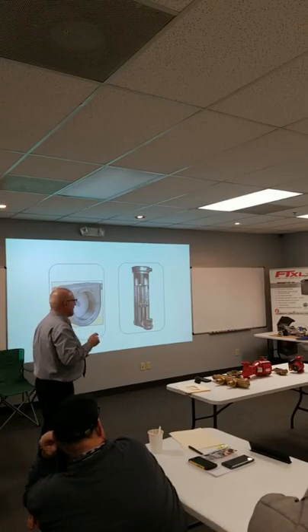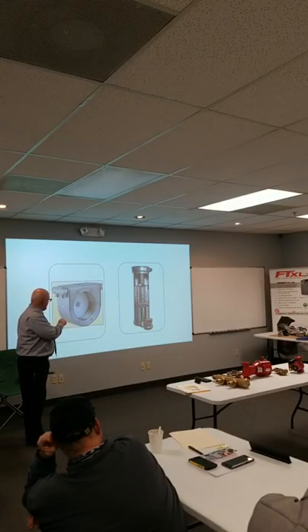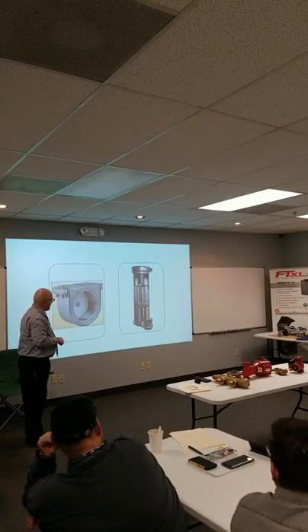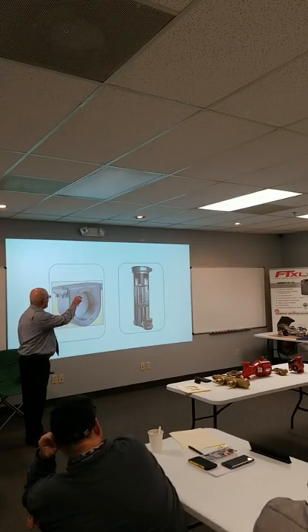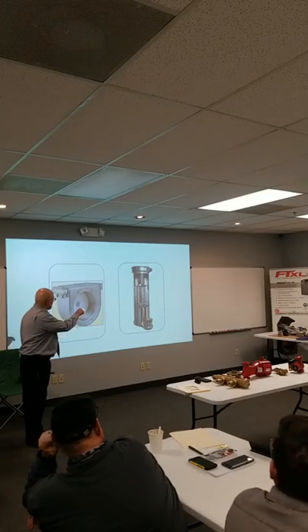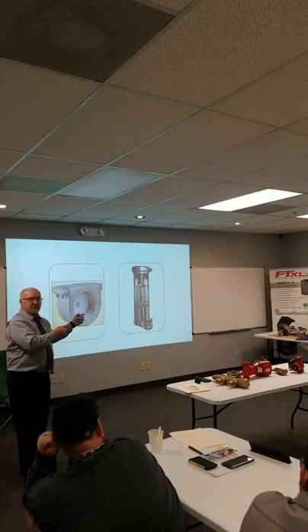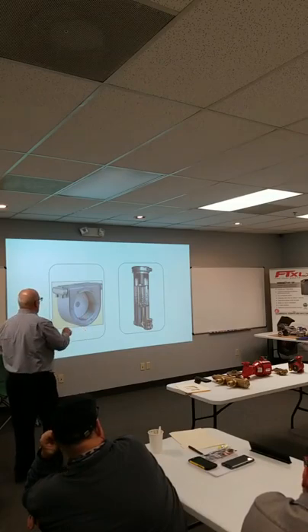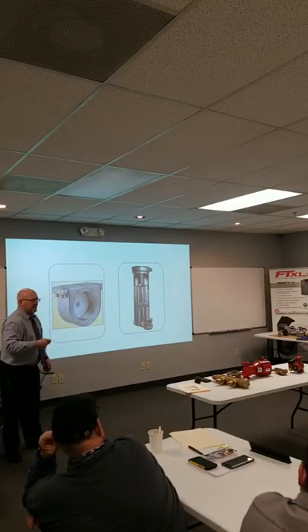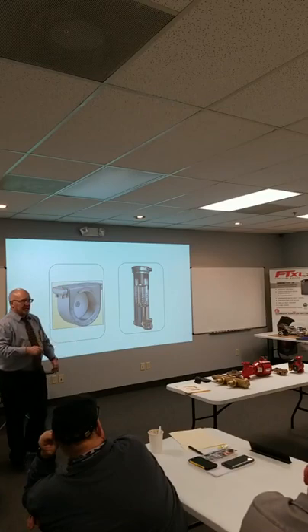So the manufacturers of condensing boilers, these types of heat exchangers, this is what we call a water tube heat exchanger. Water goes in through this manifold, goes through the tubes, and then out the outside manifold. This is a fire tube design. We fire down through the tubes. The flue gases, or elements of combustion, are going down in the tubes. The water comes in the bottom of the shell, goes through some baffles and out. Two different types of heat exchangers we're using with condensing product. There are other variations of this. High pressure drop on this one, not as much on this one. This one also has a higher water content than these.